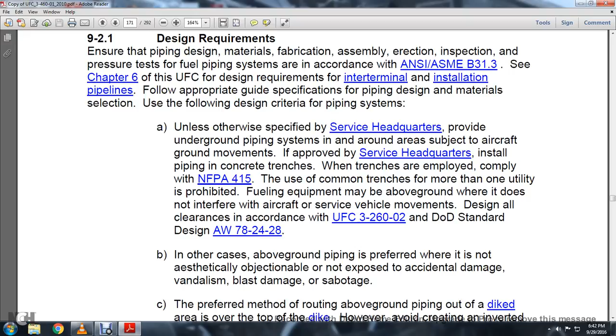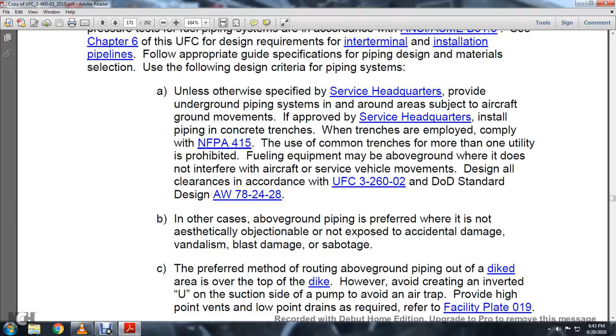The preferable method of routing the above ground piping out of the dike area is over the top of the dike, avoiding creating an inverted "U" on the suction side of the pump to avoid an air trap. Provide high point vents and low point drains as required, refer to facility plate 019.